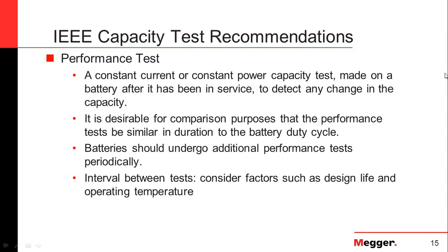A performance test is much like an acceptance test — constant current or constant power — but it is made after the battery has been in service for some period of time, typically two years. IEEE recommends that the test duration be similar to that of the duty cycle. You'll want to do these on a continuous basis; we'll get into the recommended frequencies shortly.